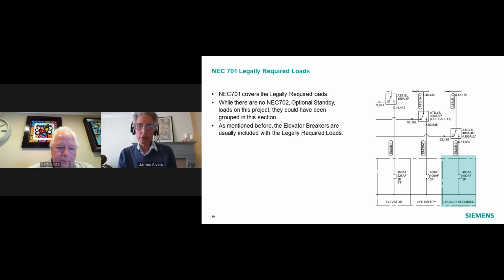NEC 701 legally required loads. This one line shows one breaker for legally required loads. It doesn't show anything for 702 loads, which are the optional standby. But if there were breakers and he had shown them in separate compartments for those loads, those breakers could be combined with the legally required loads. The particular code reference for that would be 701.10 and 702.10, which basically state that wiring shall be permitted to occupy the same raceways, cable boxes, cabinets, and other general wiring for both, and that's true for both the legally required loads and the optional standby loads.